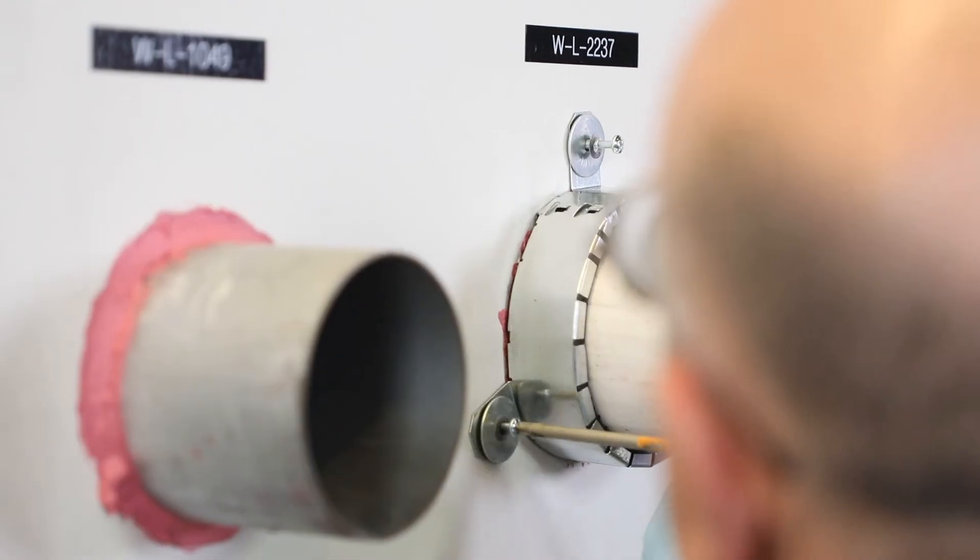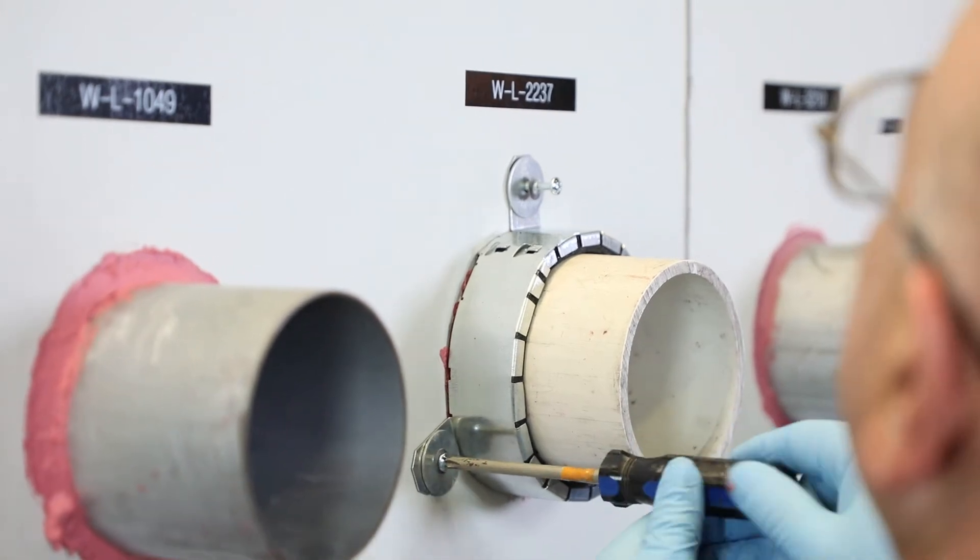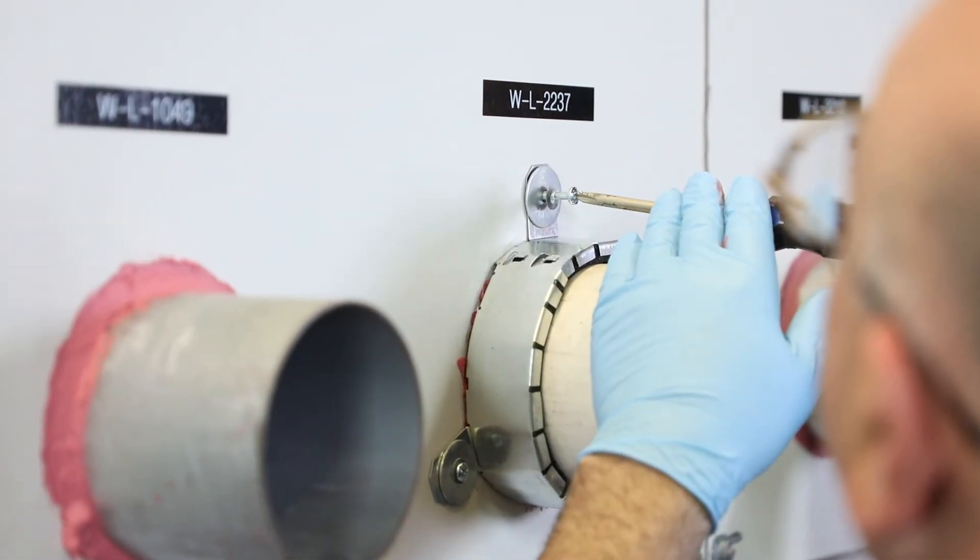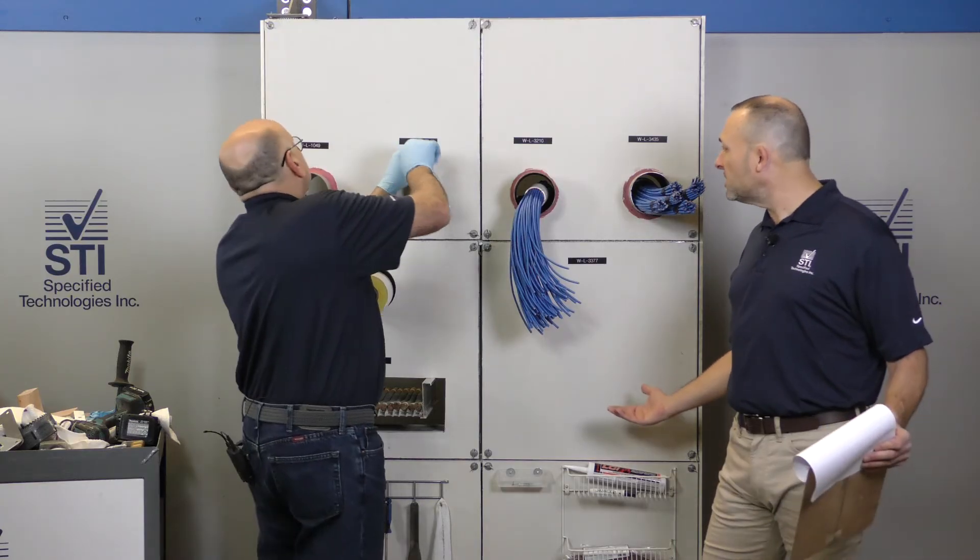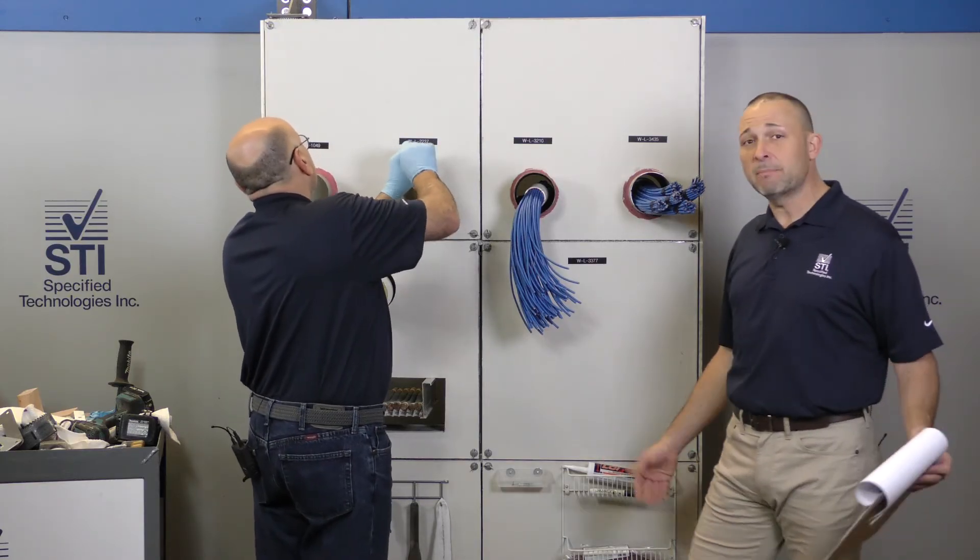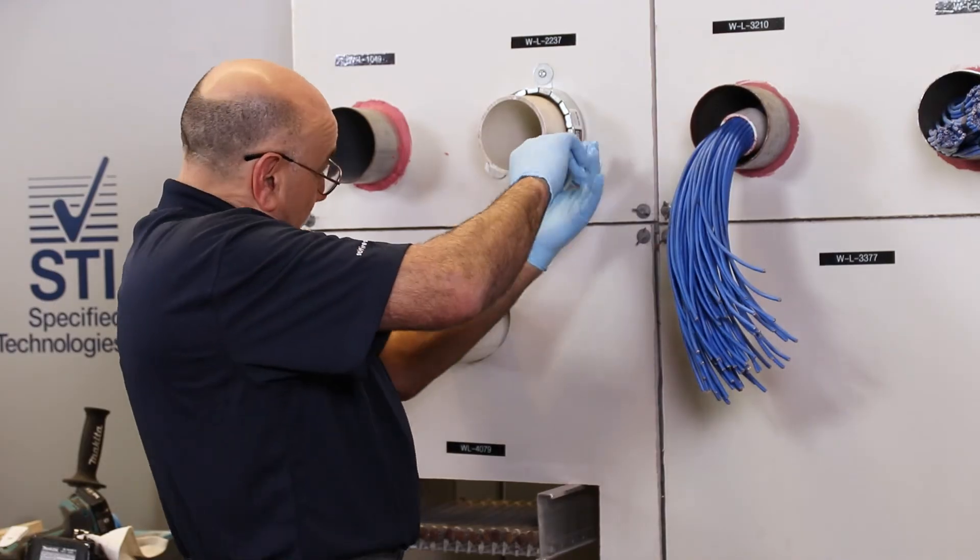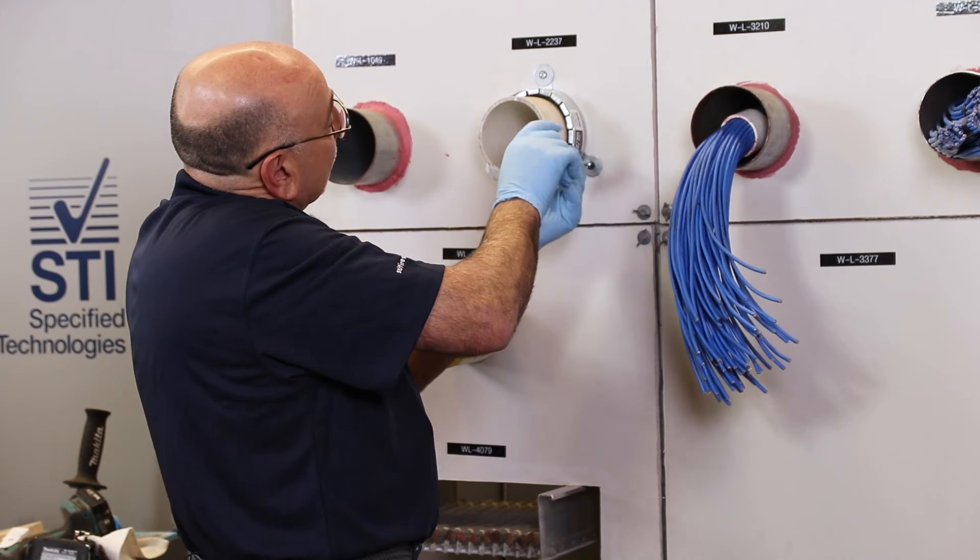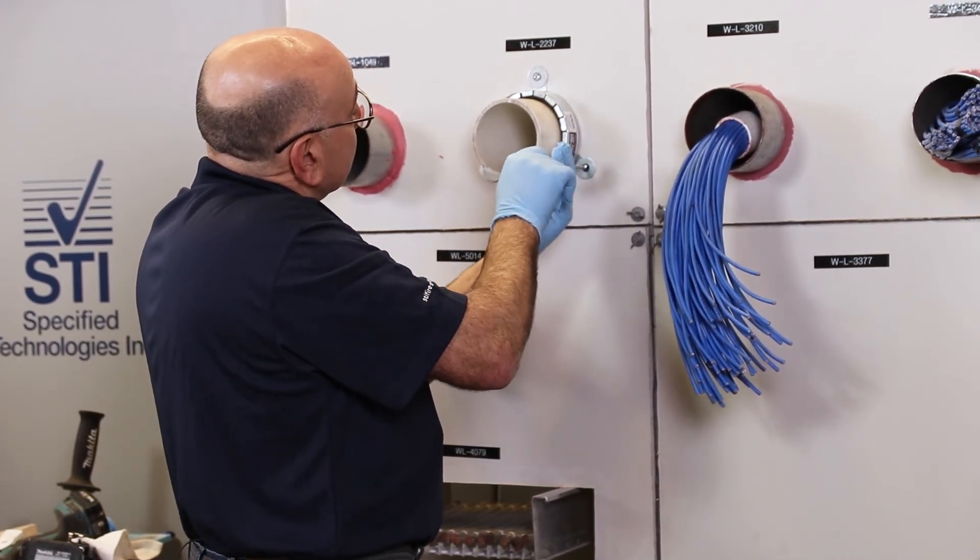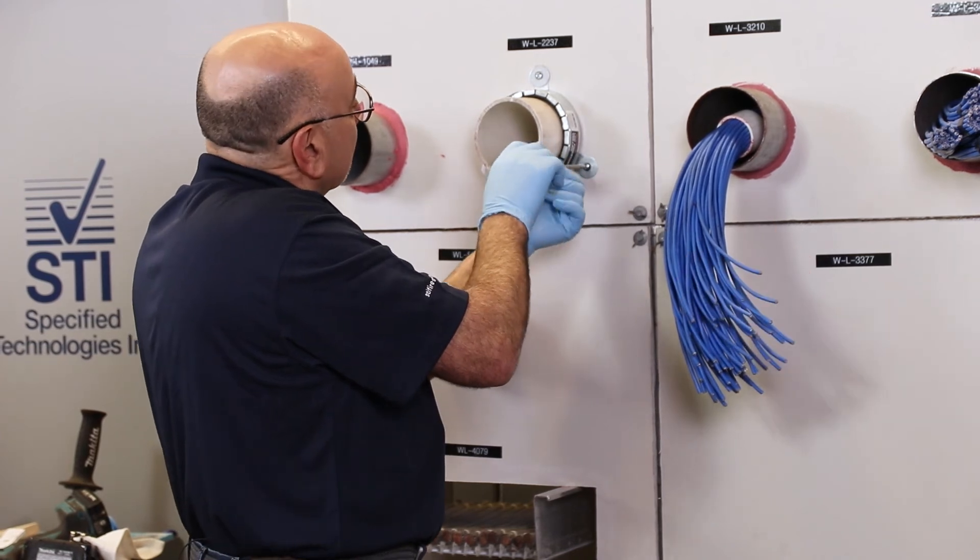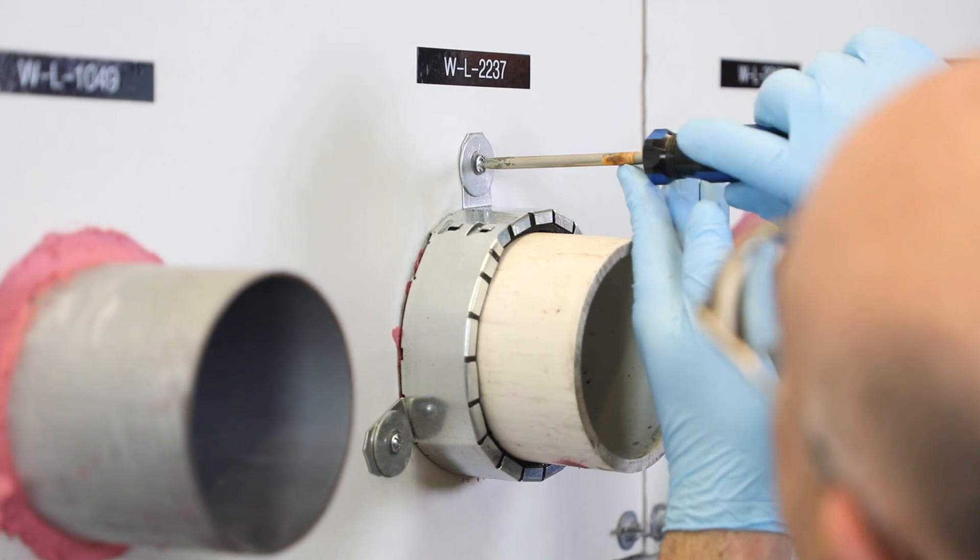Now it's worth mentioning that we needed this extra intumescent because we have such a large opening. This is a four inch opening. When you are about two inches or under, we do have caulk-only systems for plastic pipe. And then we even have some caulk-only systems for three inch plastic pipe in certain assemblies like concrete floors, as long as your hole is big enough and you have a minimum depth of sealant. But when you're dealing with anything four inches and over, you're going to need some intumescent wrap strips or some kind of factory collar for sure.